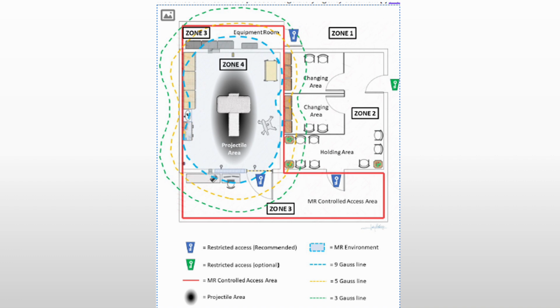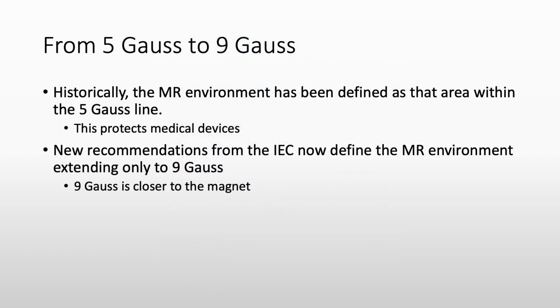This typically includes both Zone 3 and Zone 4. There is a major change with the 2024 MRI Safety Manual with regards to the MRI fringe field. In the past, we have always controlled access to areas that are greater than 5 Gauss. That was to ensure that medical devices such as pacemakers were not impacted by the magnetic field. Recent research has indicated that these devices are safe up to 10 Gauss.